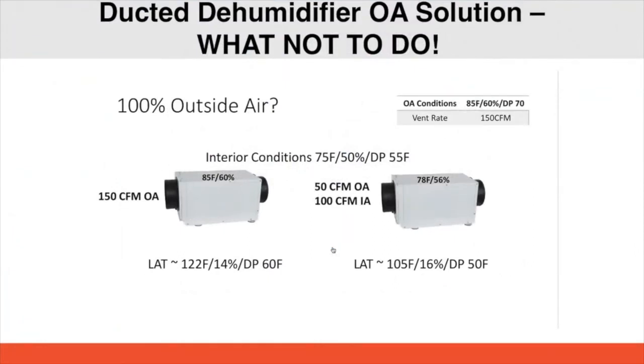A ducted dehumidifier is 100% outdoor air. We do not recommend this at all. You will not get the results that you want. Again, once the dehumidifier comes on to bring in that outdoor air, if used in this way, we have to load the coils. So there's going to be several minutes of run time that you're bringing in that.